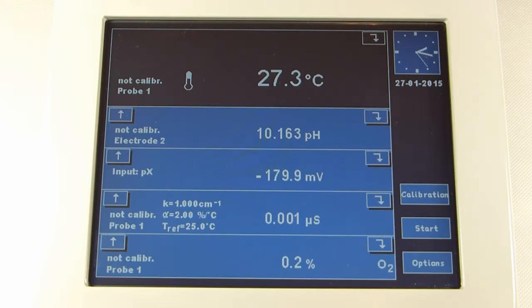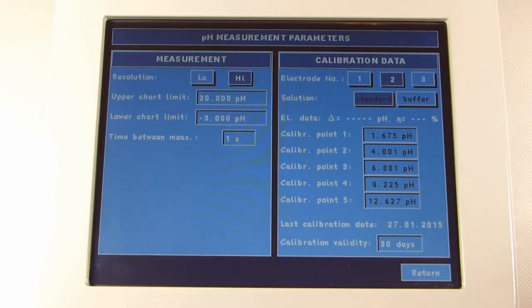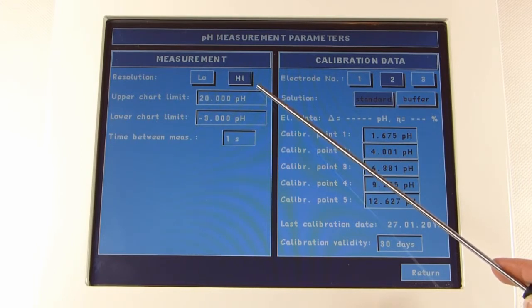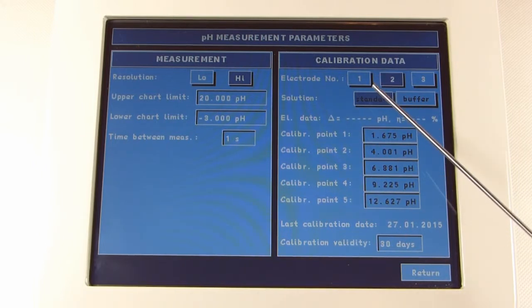From each of the chosen functions, we may switch to the screen of parameters used for setting the basic data related to this function. Choose the screen by pressing the button with arrow placed in the upper right corner. The simple menu facilitates work. For example, in the pH function, before the pH measurement, we may choose resolution high up to the third decimal place or low up to the second decimal place. Electrode number, we may choose 1, 2 or 3 symbol. We can set the calibration expiry date and check the buffer's values stored in the memory.